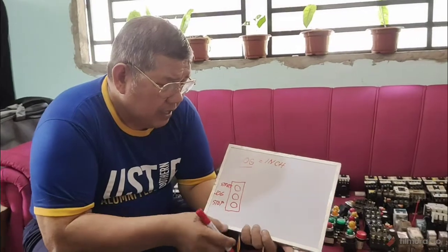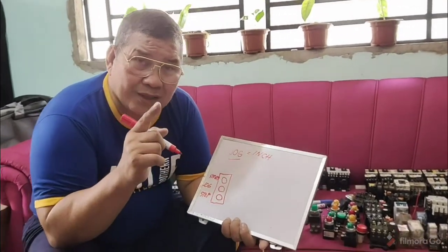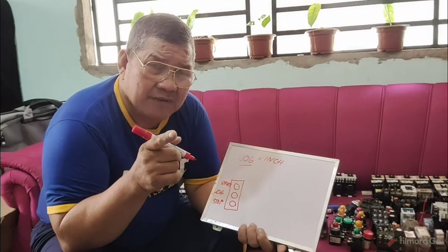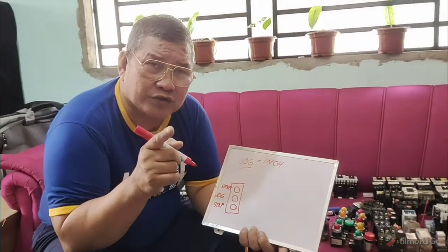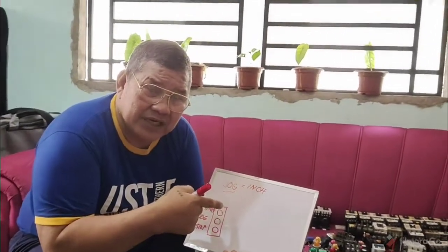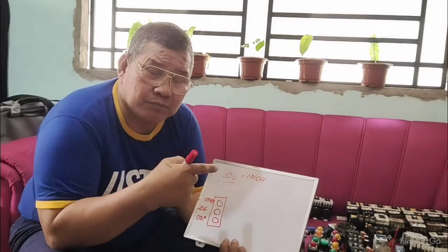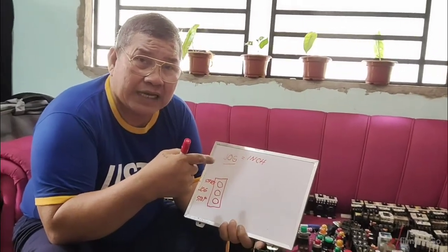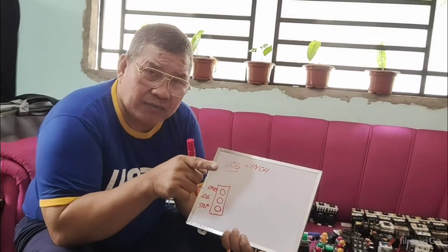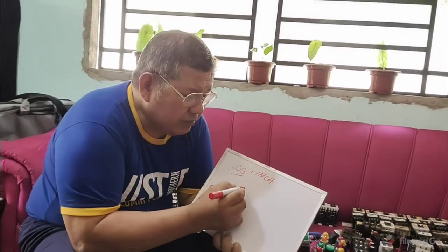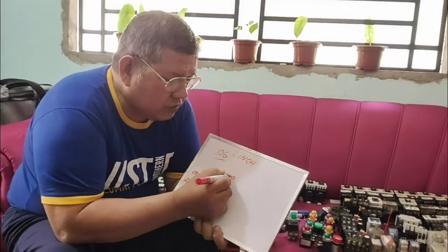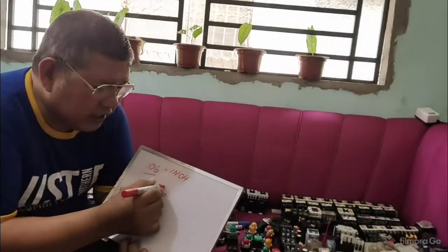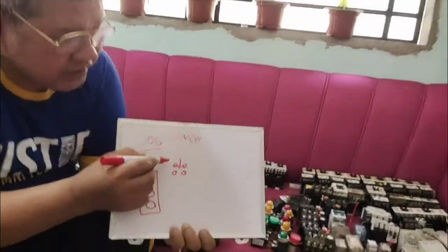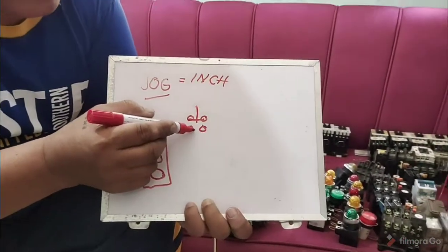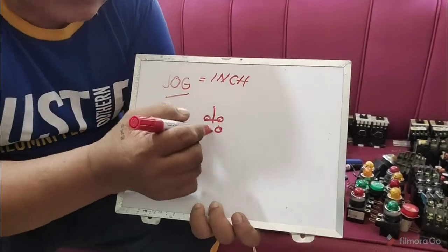By the way, in the start button, we use only one contact, that is normally open. And for the stop button, we are also using one contact, and that is normally closed. But this time, the jog button is a break button, meaning double contact. There is normally closed and there is normally open. Okay? So if you want to see the contact, for jog, you will be using this one. This is now the double contact, normally closed and normally open, and this is only one push button.